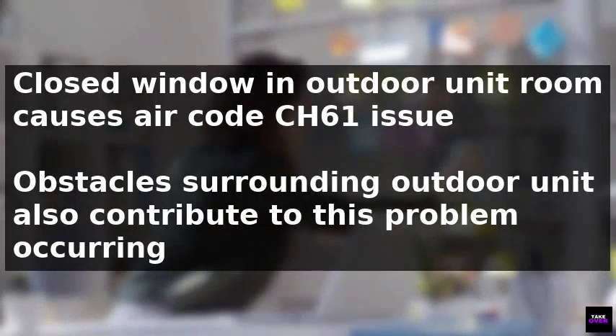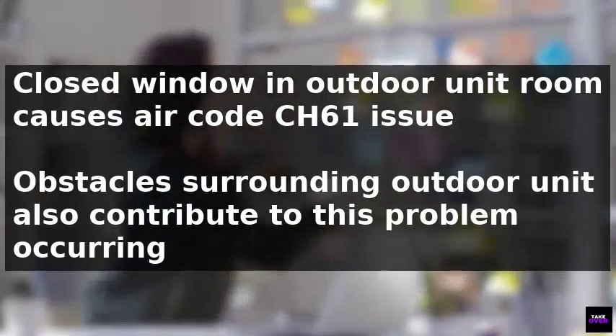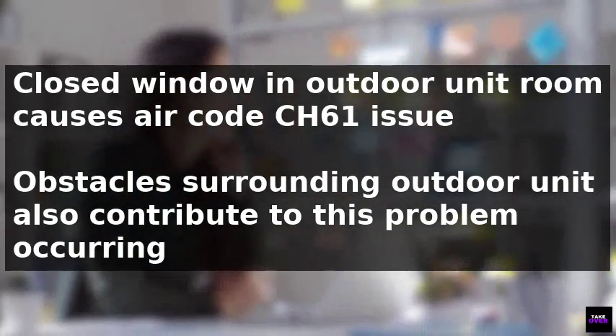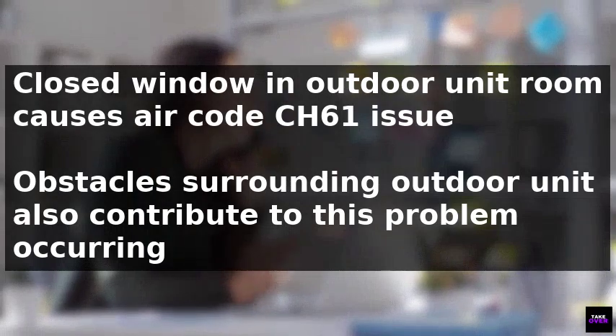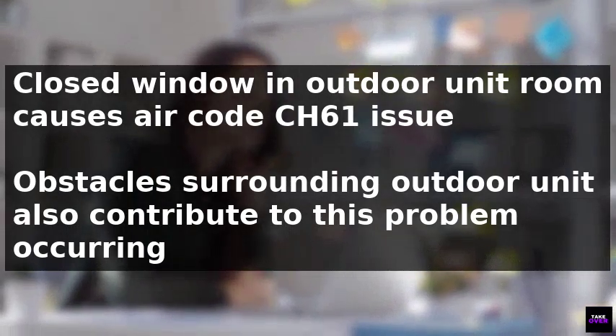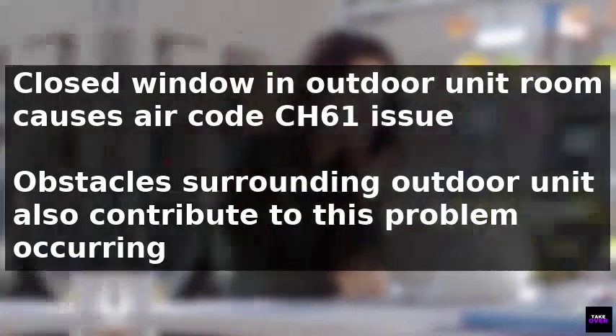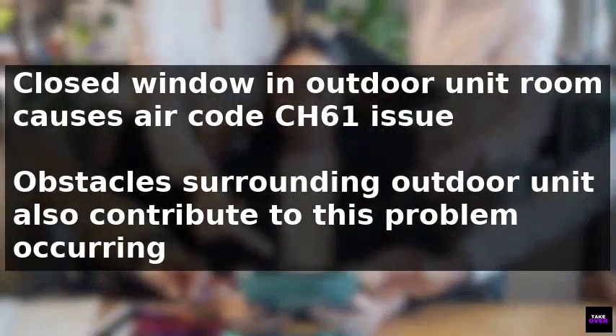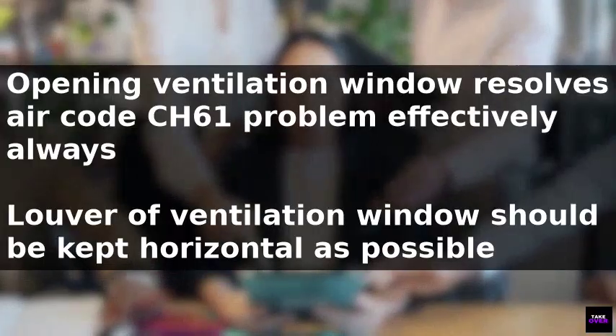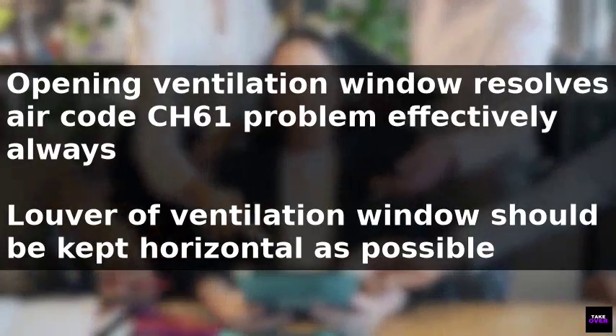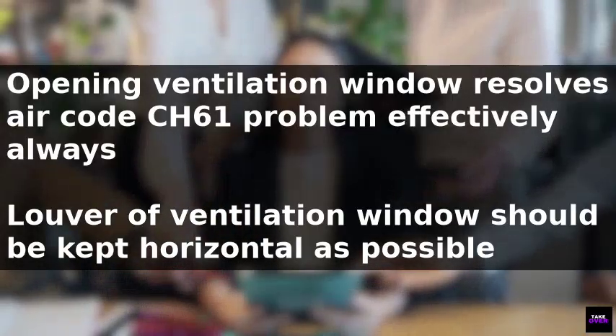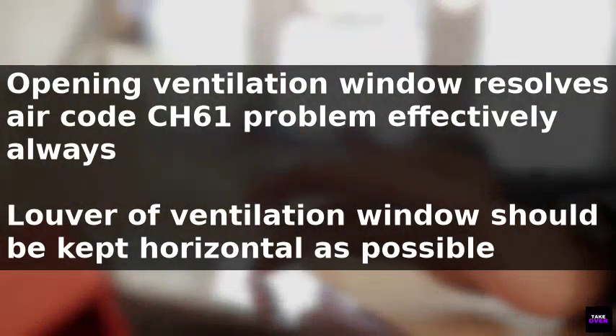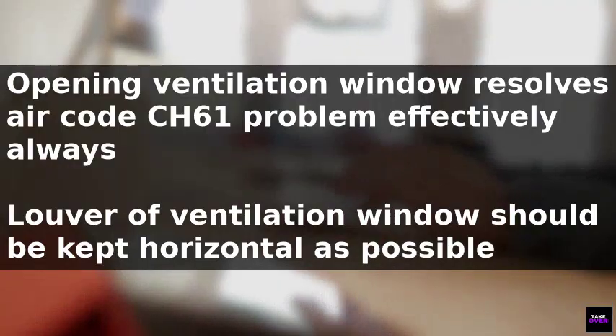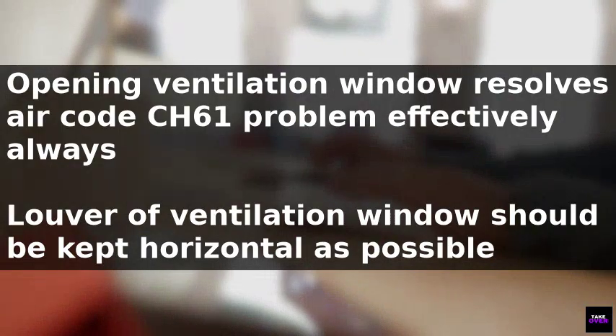To resolve this problem, it is essential to open the ventilation window of the outdoor unit room, allowing hot air to escape and preventing it from flowing back into the air conditioner when the outdoor unit overheats. The louver of the ventilation window should be kept as horizontal as possible. Additionally, removing obstacles from around the outdoor unit, including the front, rear, and sides, is crucial for ensuring sufficient ventilation.